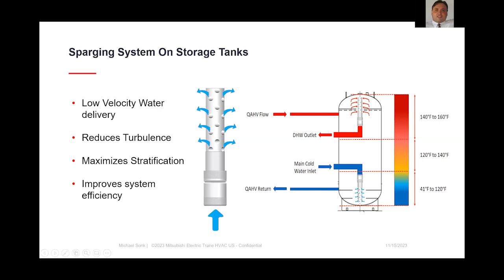And again, this is done by minimizing the effects of a normal velocity jet that would be present under a high drawdown event. So these are designed basically as cylindrical tubes with multiple perforations, usually to keep the velocity below, I think, 4 feet per second is a typical goal. And again, the goal is to minimize a jet situation, velocity jet into that tank that's creating turbulence and mixing, and maintain that thermocline.